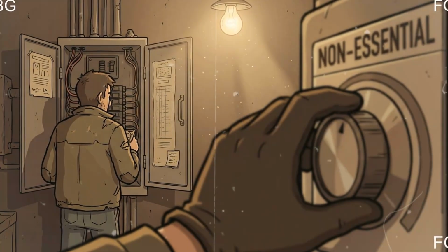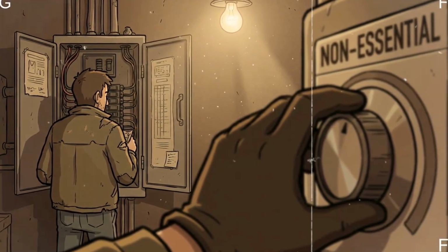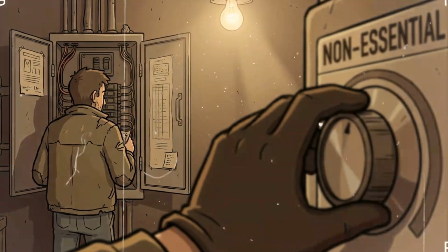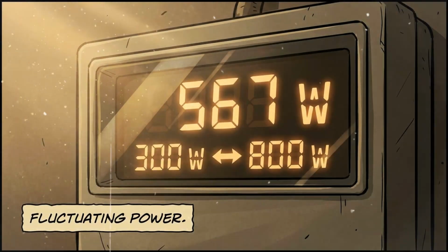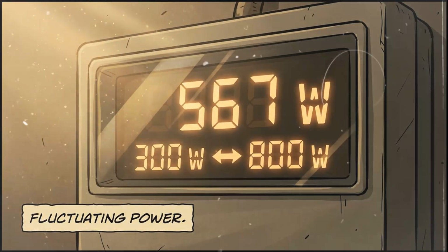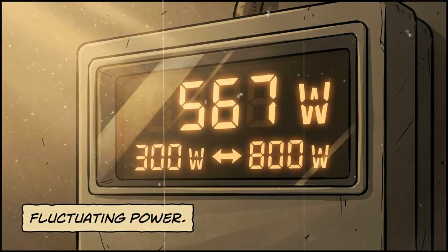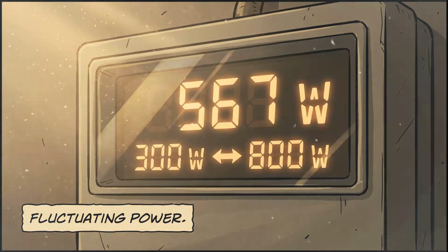The sum of your critical loads, not peak simultaneously, but staggered rotation, defines your minimum power requirement. For a typical household without medical equipment, this number is often somewhere between 300 and 800 watts, average draw across the outage, with periodic surges for compressor startups.